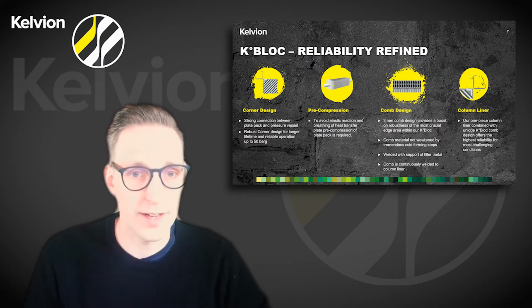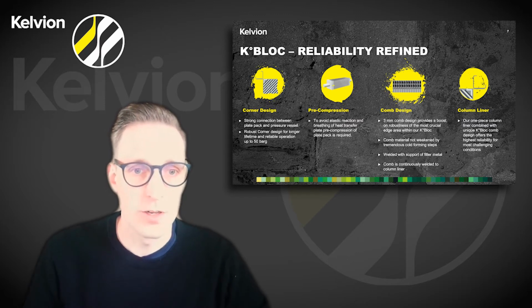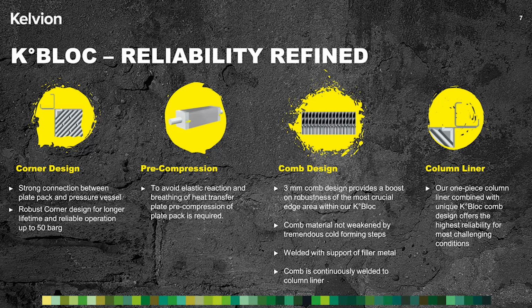The core feature of the K-BLOC is the plate pack. All previously described advantages originate from the plate pack. So, the reliability is created here, and special attention in design and manufacturing was given to this step. The K-BLOC comes with a strong and robust corner design to transfer regular operational stress reliably from the plate pack to the pressure-carrying parts. A pre-compressed plate pack is crucial to ensure solid metal-to-metal contact of each plate. The comb is, together with the corner design, the most important feature for the stability. The 3 mm comb is welded to the plate pack and to the column liner without any weakening cold-forming steps. High-quality filler material is used for those welds.